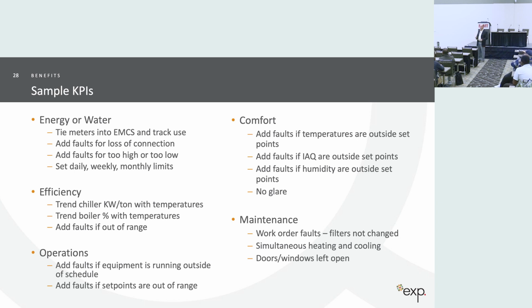Set points that are out of range. Every corporation has set points, for let's say a room. I'm sure this place wants it to be at 70, 72, whatever that is. Maybe somebody is hot and they set it for 65. And once they set it to 65, it stays 65, whether that person's there or not. You want to know those things. When we talk about occupant comfort, let's do faults for when temperatures are outside some set point. So it'll alarm me if it's not meeting something or somebody set something outside of your norm. Indoor air quality: you want to make sure that people are healthy. Well, why not set up faults if something happens? Humidity, and then even glare.